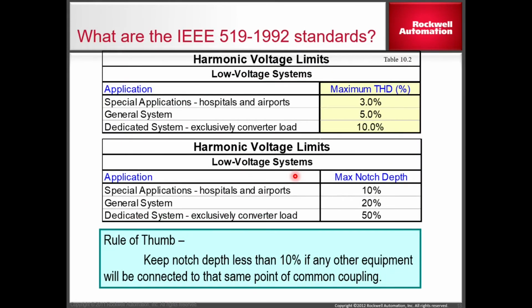So they came out with IEEE 519, which gives us some guidelines on where our total harmonic distortion needs to be and still be within considerable operating ranges. As you can see, in hospitals and airports, they want it down to 3%. General industry, 5%. And if you have a section just dedicated to drives only, you can go up to 10%.